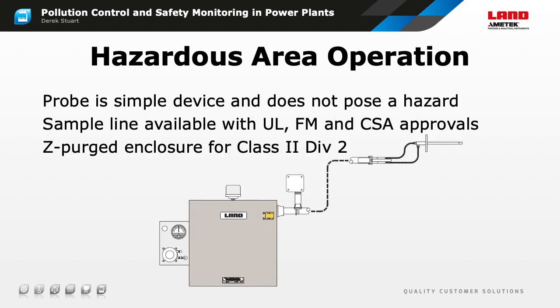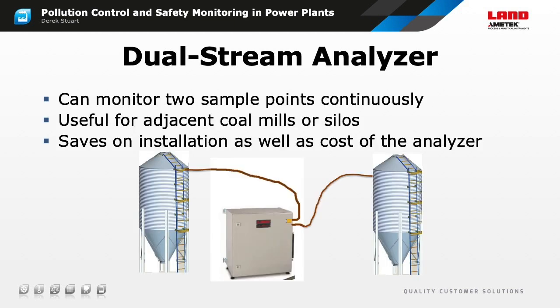The inside of a silo is generally considered to be a hazardous area, but this does not cause us any problems because the only thing inside the silo is the stainless steel sample probe, and it is classed as a simple device. In cases where the analyzer has to be mounted in the hazardous area, a Z-purge allows it to meet Class 2 Div 2 specifications. A dual stream analyzer allows simultaneous and continuous measurements from 2 adjacent silos. In addition to the savings on the cost of the instrument, reducing the number of cabinets saves significantly on the installation costs and on the amount of space needed for the installation.